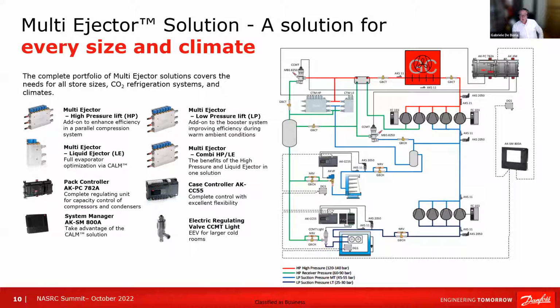One is the high pressure lift, an add-on to boost efficiency in the standard system with parallel compression. We then have the low pressure lift model, which is mostly used to improve efficiency in applications in warmer ambient conditions. We have a liquid ejector that allows the application of our solution called CALM, which I will show in a few minutes. And there is a combination of the high pressure ejector and the liquid ejector for more advanced installations, but which can grant the installation the benefit of both ejectors.